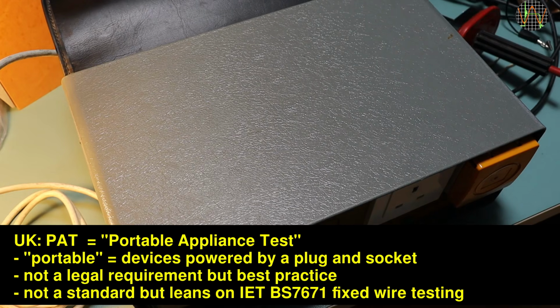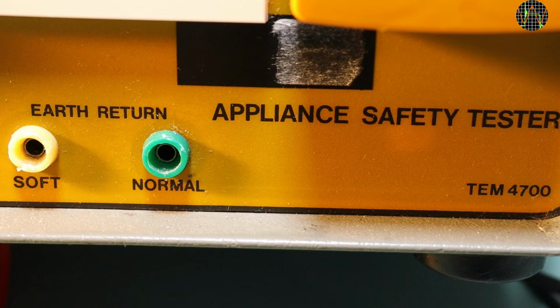So let's do that. Part of these tests is to check if the appliance is properly earthed, and here we have two sockets for earth return, one labeled soft and the other normal. The soft one should be seen in the light that the earth test purposely uses high currents to flush out weak earth connections. Fine for toasters and kettles and the like, but modern low power electronic equipment is generally not designed for such currents. The soft socket probably provides a test with lower current.